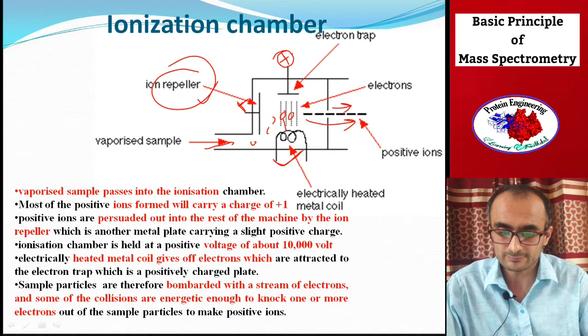Then you have an ion repeller that is also positively charged. In fact this entire ionization chamber is kept at a high positive electrode potential. As a result, the positive ions formed here are repelled by the ion repeller and directed in one direction, so that together these positive ions form a beam of ions which can be studied further on.